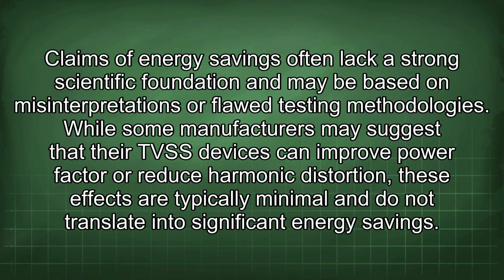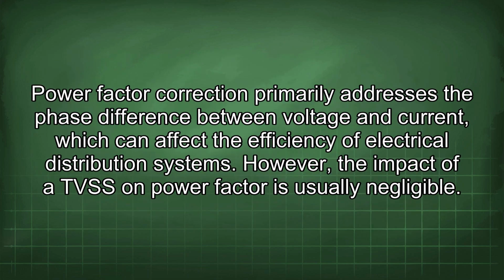While some manufacturers may suggest that their TVSS devices can improve power factor or reduce harmonic distortion, these effects are typically minimal and do not translate into significant energy savings. Power factor correction primarily addresses the phase difference between voltage and current, which can affect the efficiency of electrical distribution systems. However, the impact of a TVSS on power factor is usually negligible.